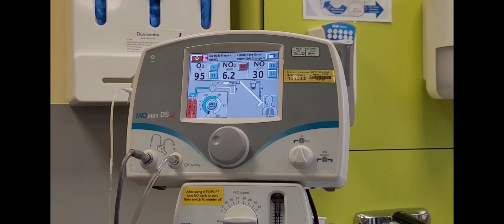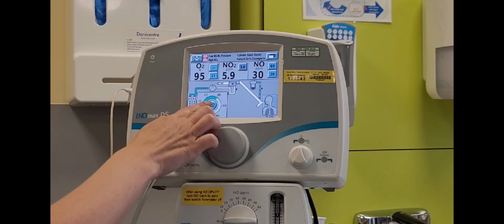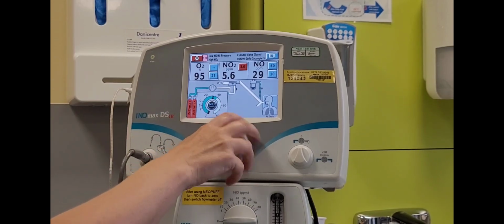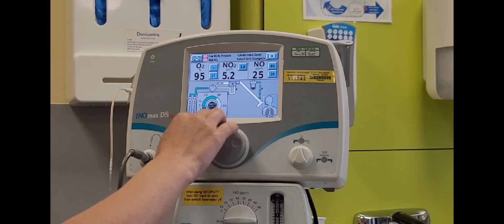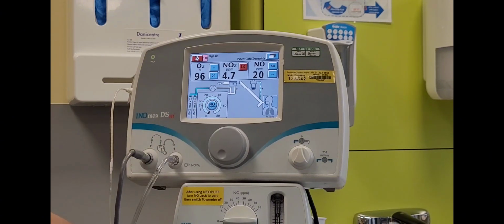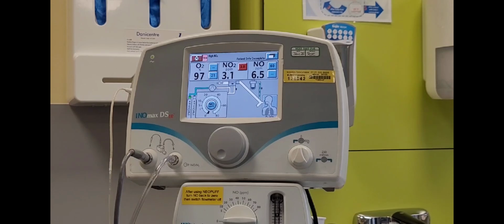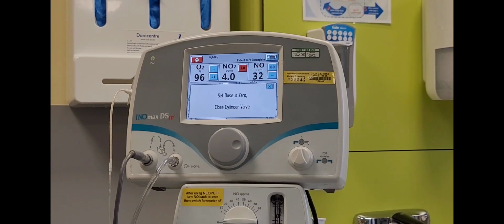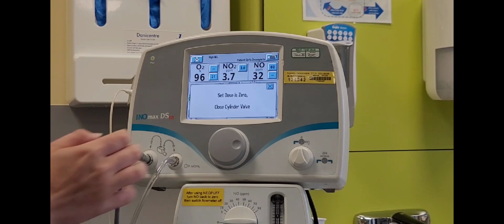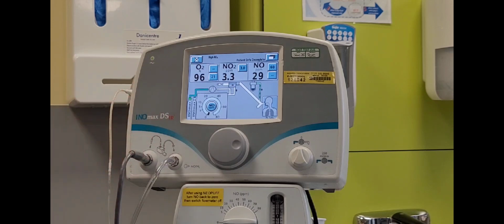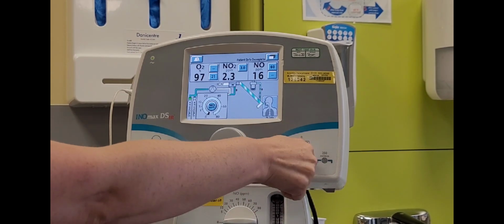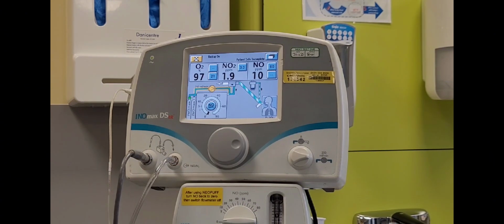Now open the cylinder valve and turn the INOmax dose to 0. You should get a set dose is 0, close cylinder valve alarm. At this point, do not close the cylinder valve. With your oxygen still on, it is time to test the backup delivery. Turn backup delivery on here and check that the backup delivery alarm has been activated.